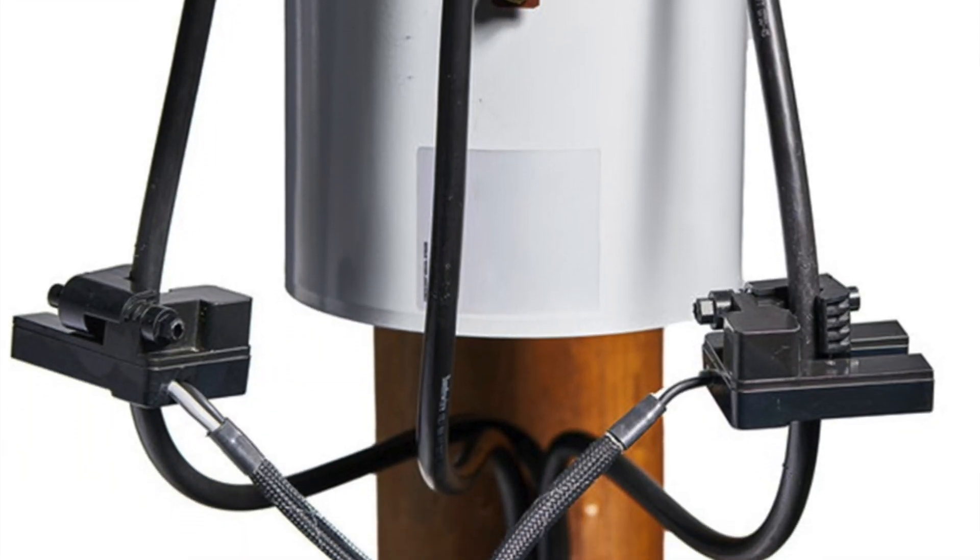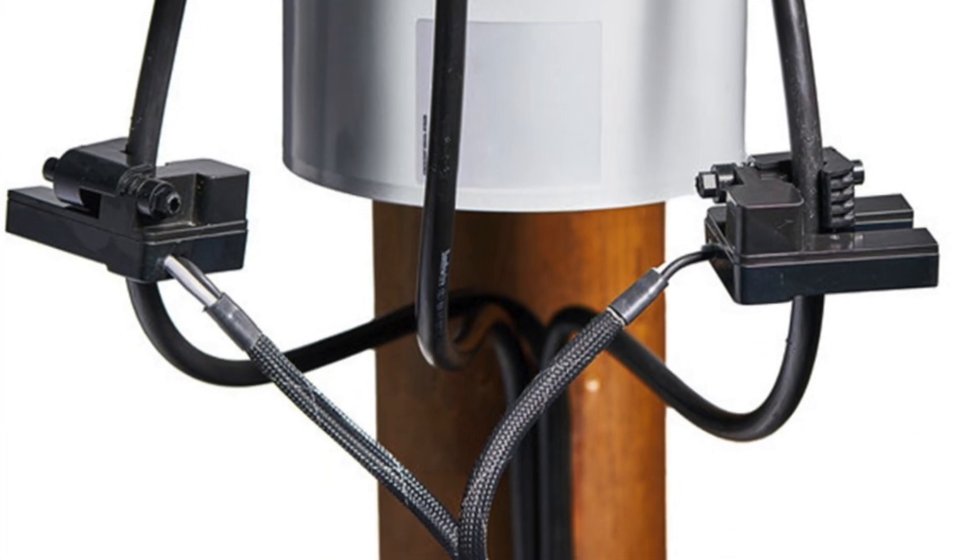This is essentially just another electricity meter, but it's installed up at the transformer. So if we have a situation where somebody has set up a bypass to their electricity meter, we can tell how much electricity they've been using that hasn't been getting measured at their meter.